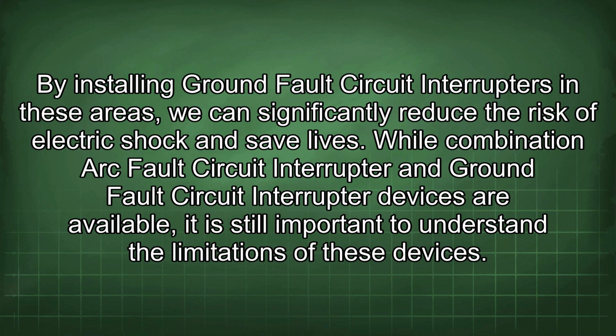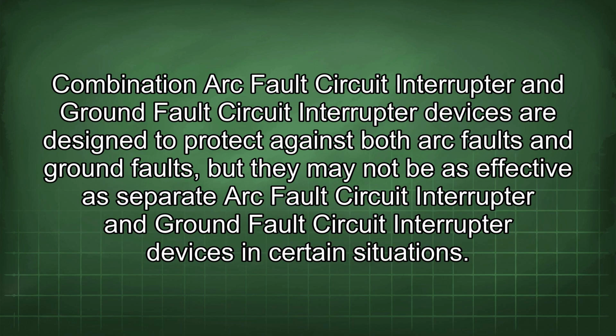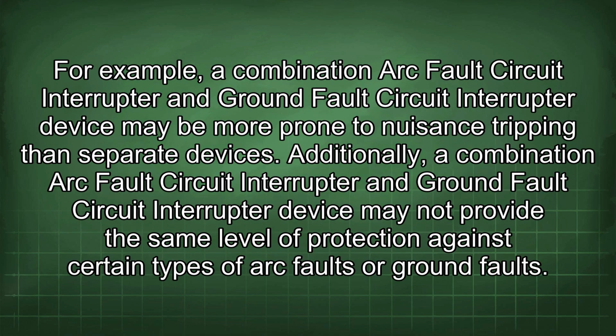While combination arc fault circuit interrupter and ground fault circuit interrupter devices are available, it is still important to understand the limitations of these devices. Combination devices are designed to protect against both arc faults and ground faults, but they may not be as effective as separate arc fault circuit interrupter and ground fault circuit interrupter devices in certain situations. For example, a combination device may be more prone to nuisance tripping than separate devices. Additionally, a combination device may not provide the same level of protection against certain types of arc faults or ground faults.